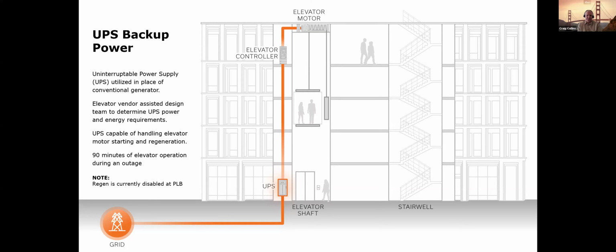That UPS serves the elevator controller. I think we have the machine-roomless type of system, where the controller is in the jamb at the top level, so on the 5th floor. And then there's an elevator motor and sheave at the top. And we power the system fully with the UPS at all times.